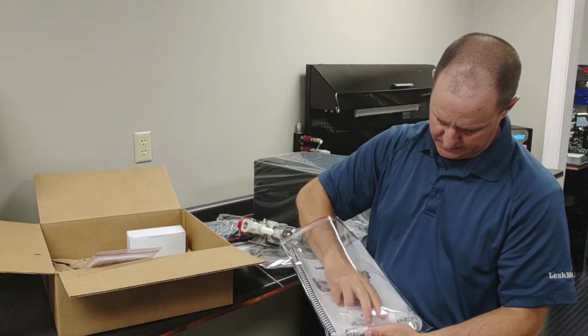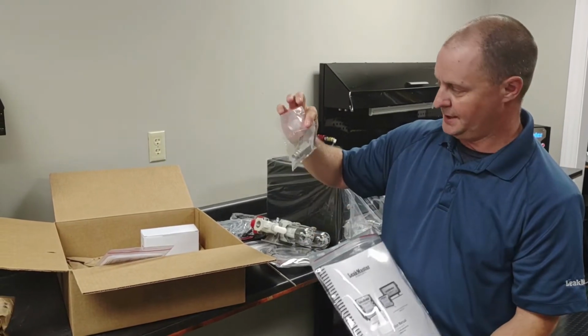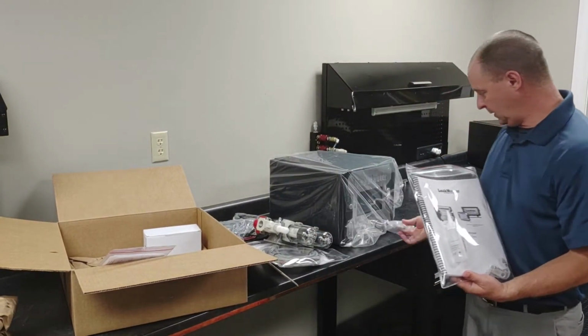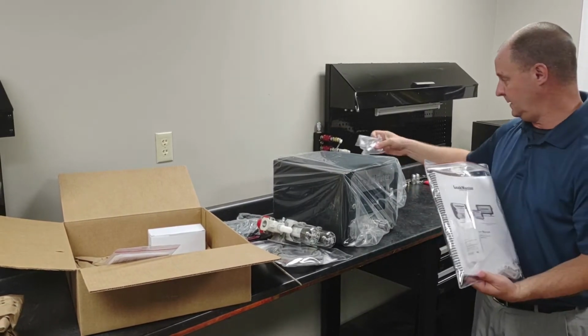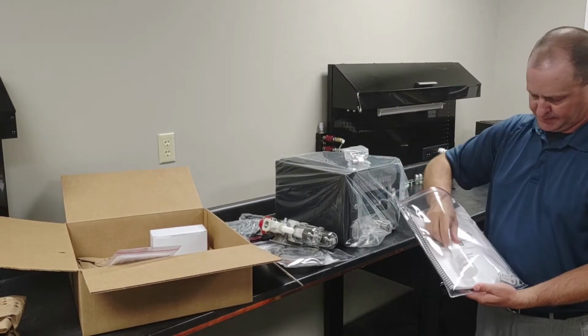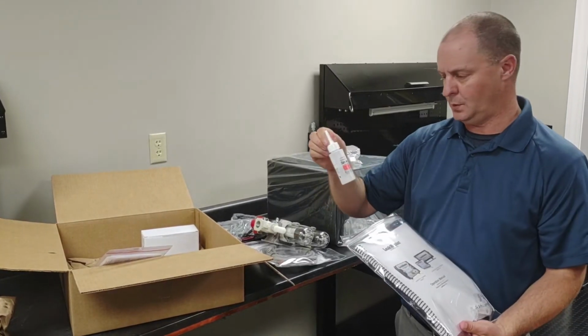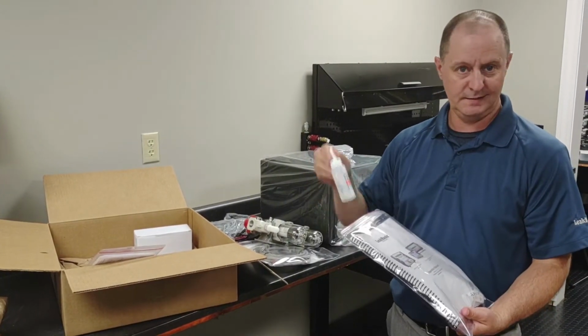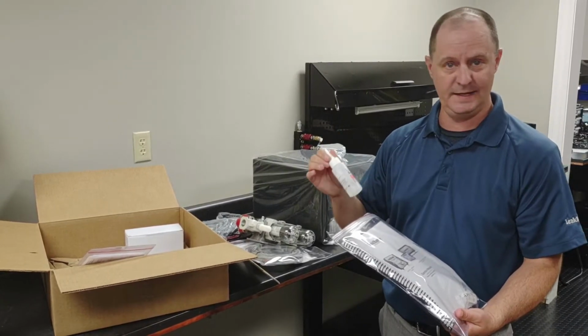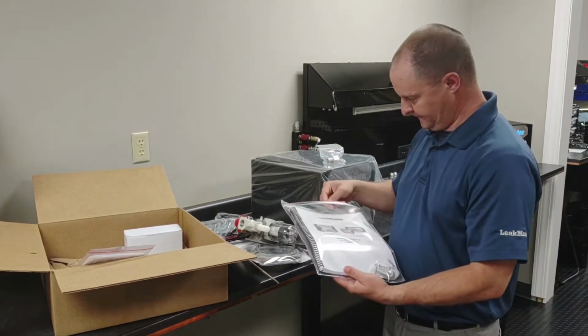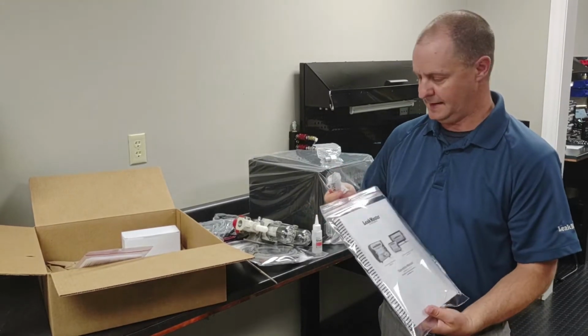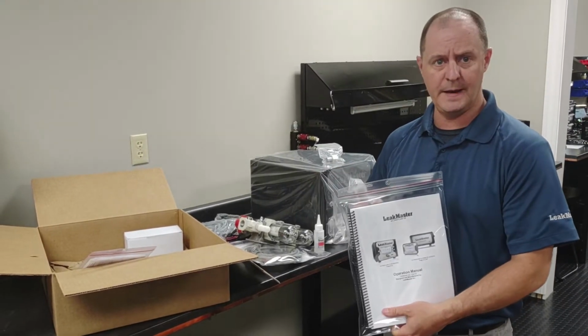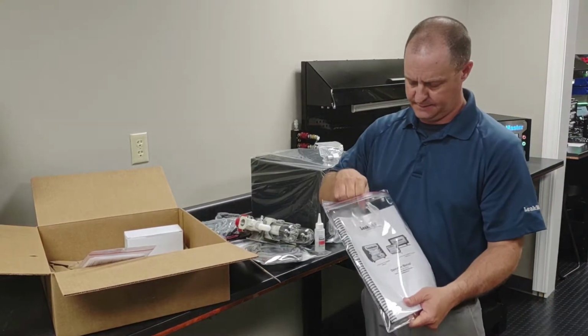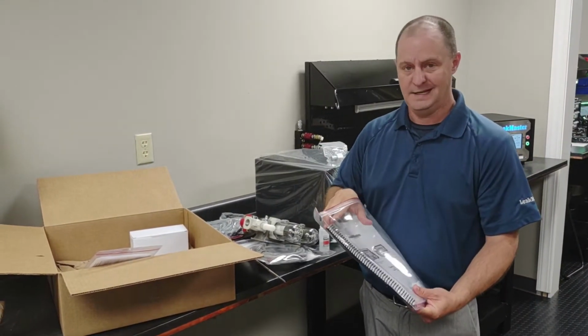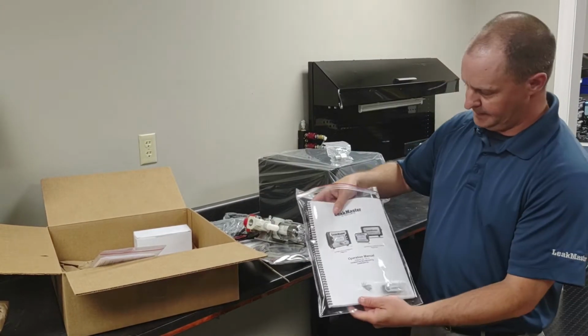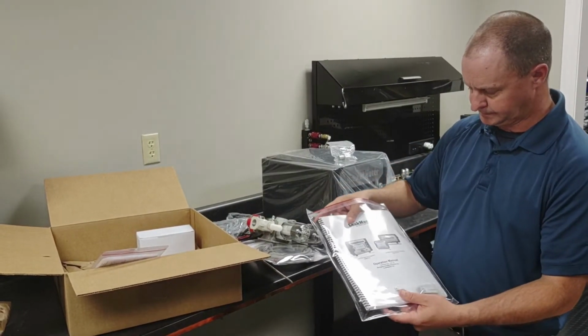You also see that we provide a Swagelok stem fitting, which will plug directly into the front of the tester, and that will be what supplies the air out to the product being tested. A bottle of Snoop for starting up and troubleshooting, looking for leaks on your seal tooling and any fittings that you have in the leak test circuit. A USB stick, which is going to have an electronic copy of your manual. It's also going to have 3D models, 2D drawings, EDS files, stuff like that. And then you've got the actual hard copy of your manual as well.